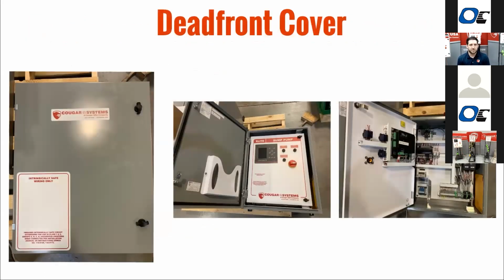The deadfront design is a great option for any of these panels that are going to be either outside or in a place where people can walk by and touch the controls where they shouldn't. We have the outer enclosure here, the outer door, that can be locked. And on the inside, we have the actual door, where you have the operators, the screen, and things like that. If it's outdoors, it's being protected from the elements when you have that dead front cover. And say it's in a parking garage, you can't just walk by and turn the pumps on and off if you have that exterior cover. You can see behind the secondary door it looks like the normal control panel on the inside.